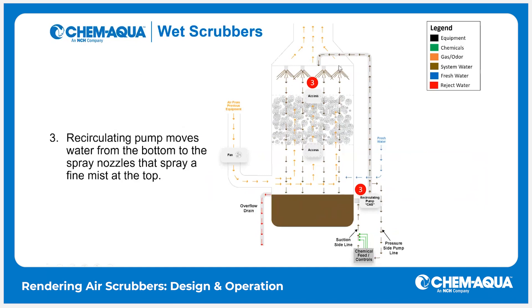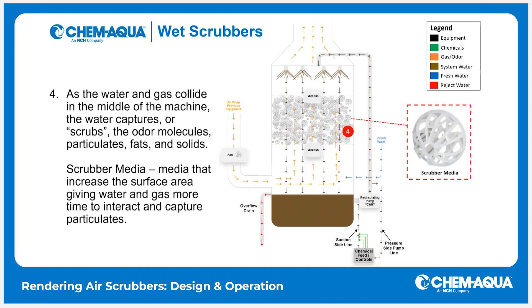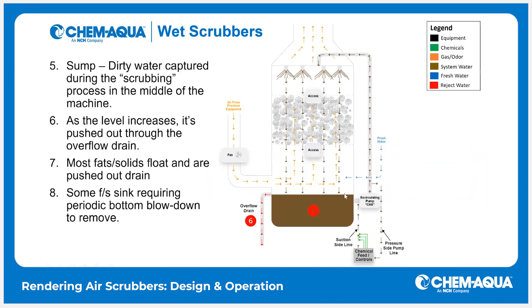It's important to make sure your recirculating pump is working at all times. As the water and gas collide inside the machine, the water cools things and captures the fats and solids with the help of media increasing the surface area. Those then drop out to the bottom into the sump, where we capture the dirty water, fats, and solids. As that sump level increases, the water is pushed out through an overflow drain or blown out through the recirculating pump side. Most fats and solids float, so we can push them out through an overflow drain.